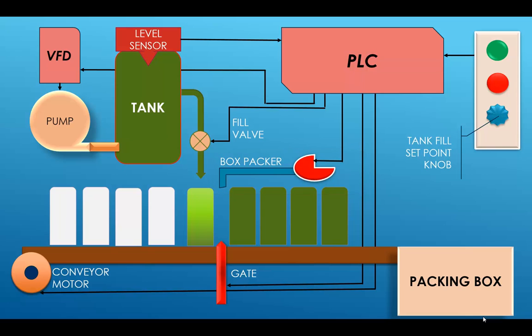So if we look in the top left hand corner you've got your tank and your fill process. The pump is connected to a variable frequency drive so you can vary the speed of the pump and the pump rate. We have our level sensor which will vary from 0 to 1023. 0 being empty and 1023 being the tank full. You will scale that in your program from 0 to 100.